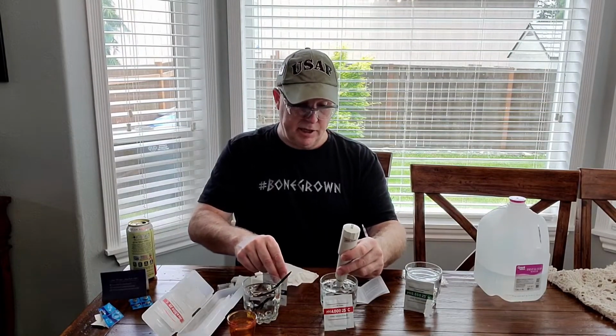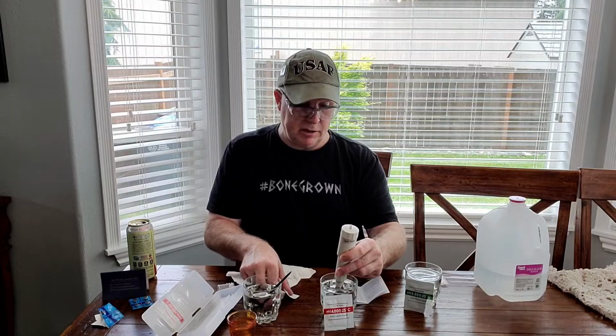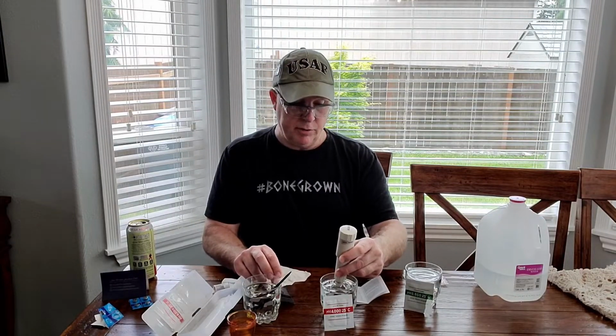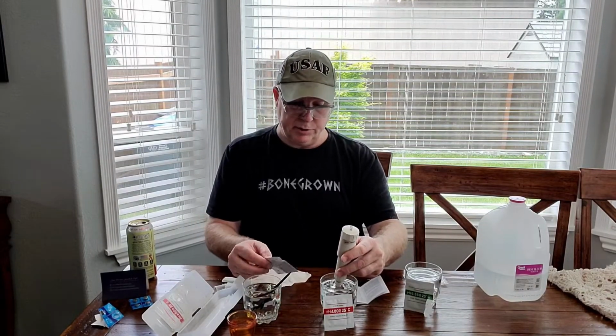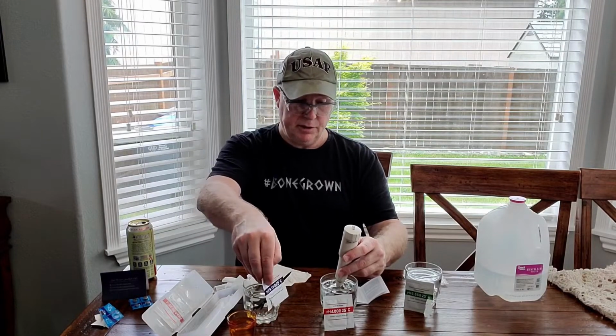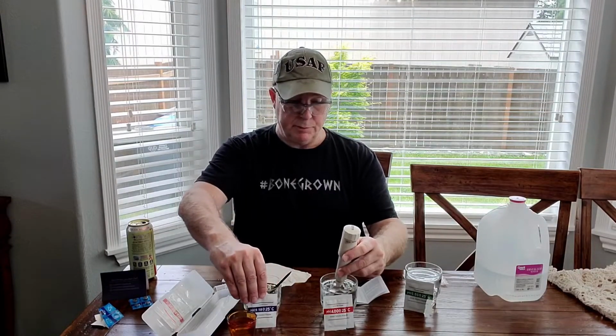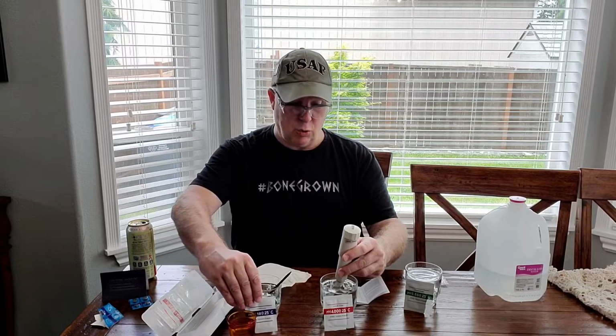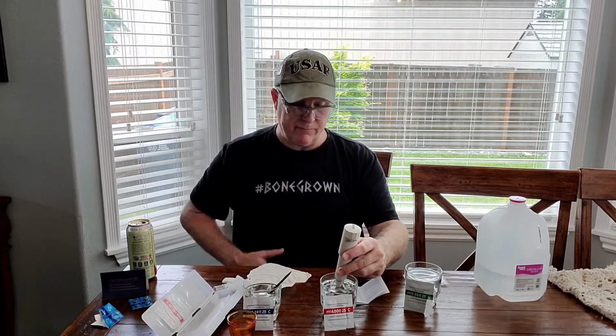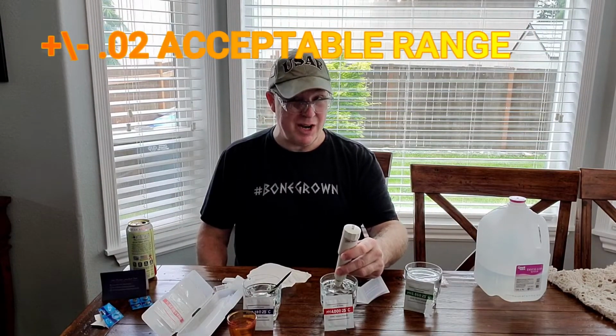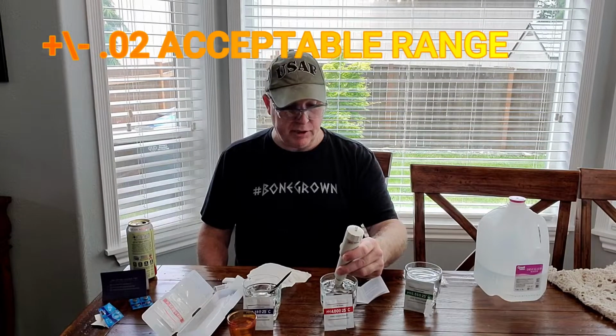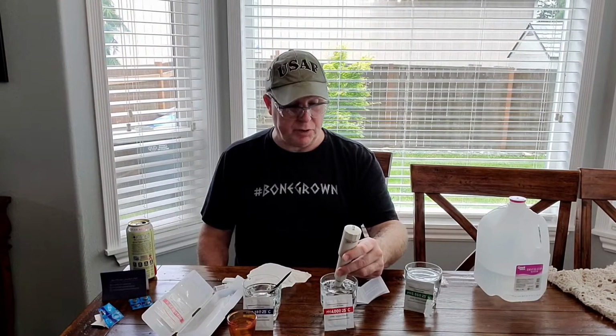and it's actually dialed in pretty good, but I'm going to go ahead and hit calibrate. I'm going to release it. It's going to go through its calibration process. It's memorizing 4.0. So this one's right on 3.99. That's within 1/100th of a percentage of that pH. I'm pretty happy with that.